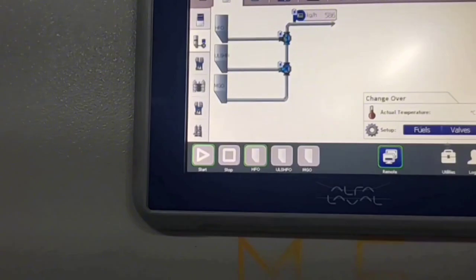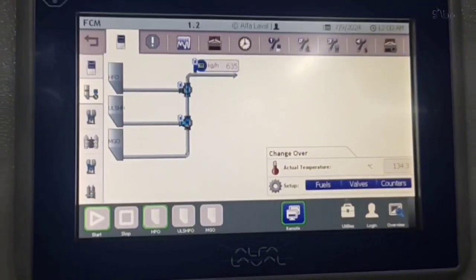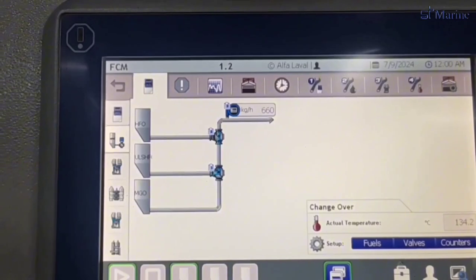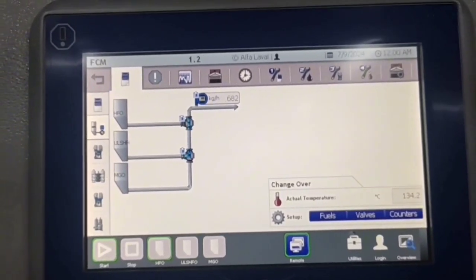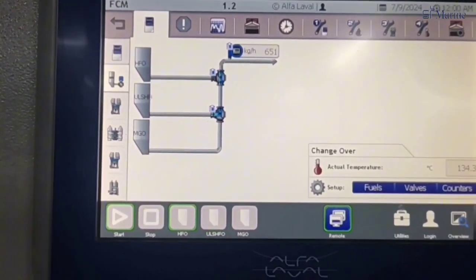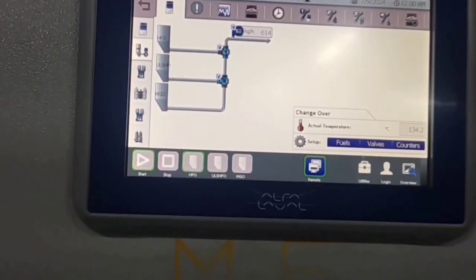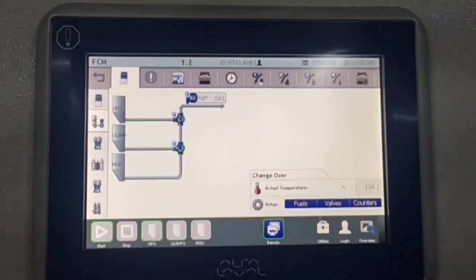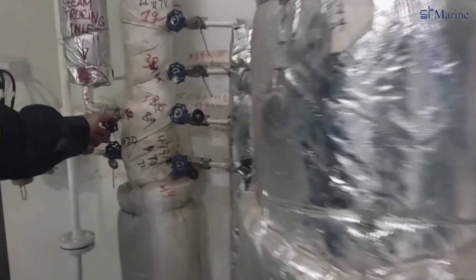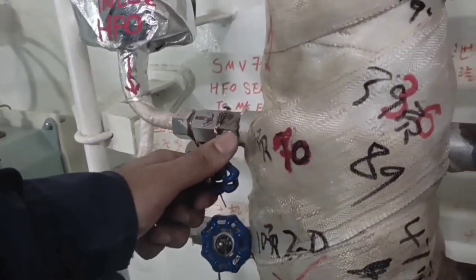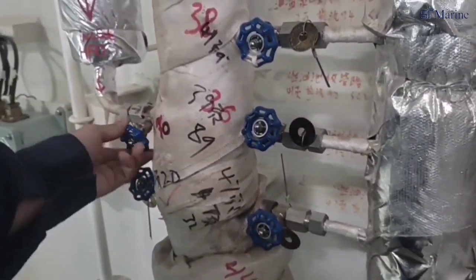How many minutes until this one stops blinking and the other takes over? The time duration is not fixed — it depends upon the density of the oil and other factors. Normally it may take 30 to 40 minutes. Now we are already in low sulfur oil, so we can close the steam tracing for the high sulfur oil. This is the steam tracing for high sulfur — the inlet needs to be closed. Now it is already closed. And this is the outlet — we are closing the outlet as well.